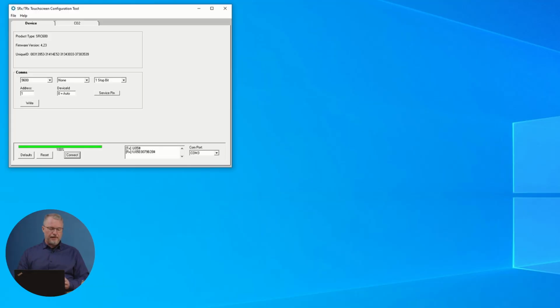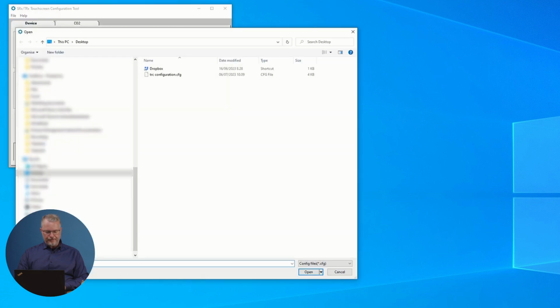Perfect. Now it's 21. Okay, let's imagine we have a building floor with 40 devices that we need to have the same configuration inside. Sounds like big work for me to do, specifically if you have many parameters that you need to change. So then I can go back to my software, connect to the new device. And instead of save, I choose the open. And I take the same file that I have stored.